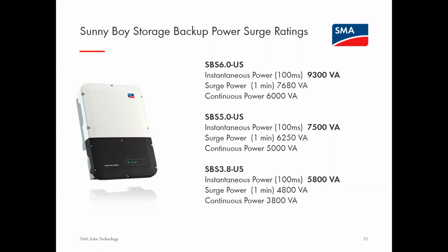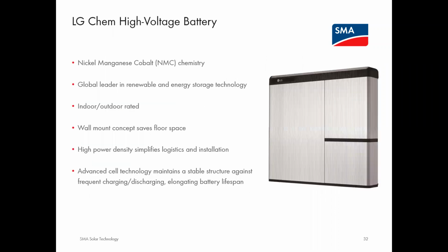A great example of that is any kind of pumps or motors. Pumps is probably the most typical example I can think of, where you've got a mission critical load that you need to power, but it requires quite a high spike, short duration, but quite a high spike in current in order to bring that motor online. So that's definitely one of the tremendous advantages of an AC coupled architecture: you get more power and you can very easily retrofit existing PV plants.